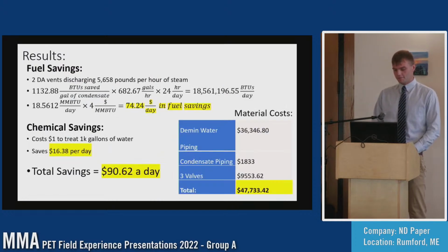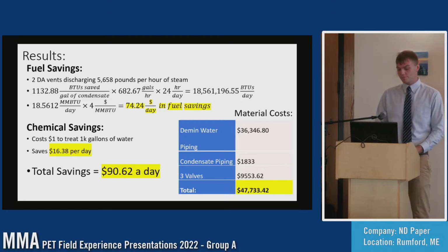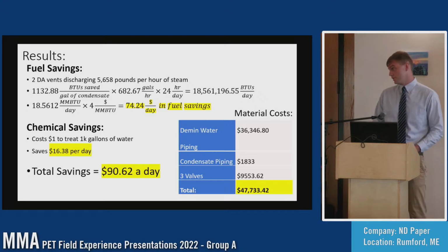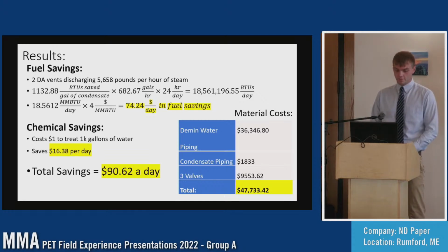So I realized that since we have such a high flow of demin water going through, the steam coming out of the DA isn't really enough to heat up the demin water. It's such a small amount. So instead I ended up figuring out the fuel savings by using the condensate instead of using demin water. There's just under 5,700 pounds of steam coming out the vent per hour, which condensed down comes out to 682 gallons. And if you take the difference of the steam condensate temp versus the demin water temp, it comes out to 1,132 BTUs saved per gallon of condensate used.